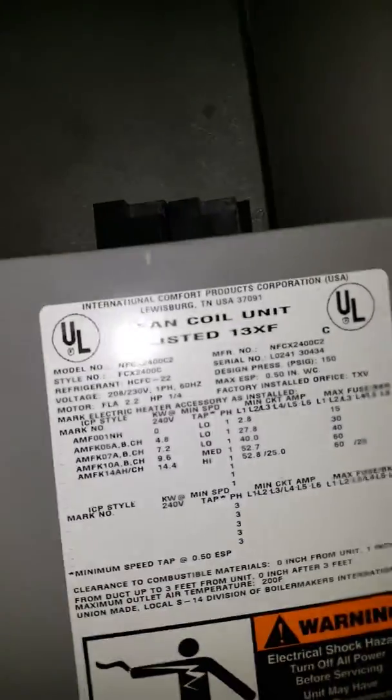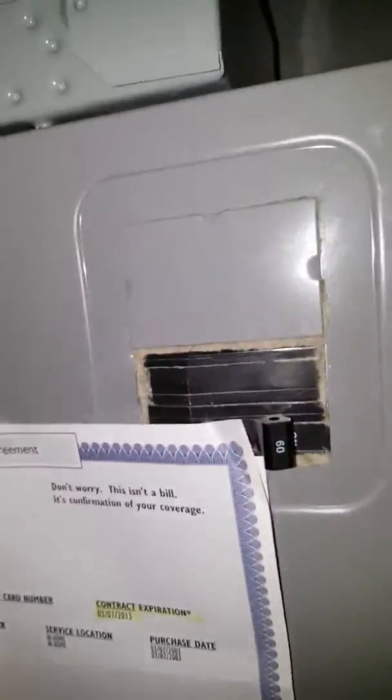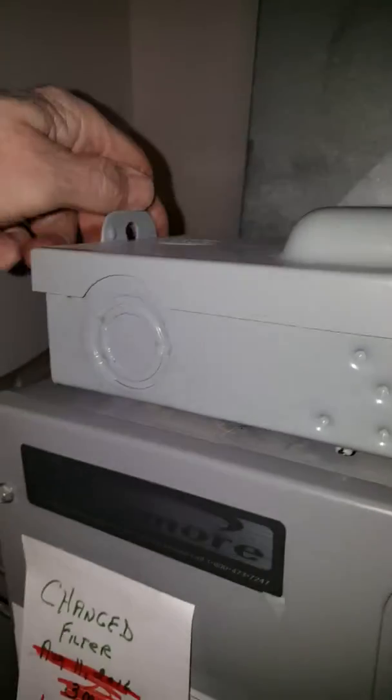This is a two-ton unit, two-ton outdoor unit. It has a 60-amp breaker and there is a disconnect on the top — no fuse disconnect.